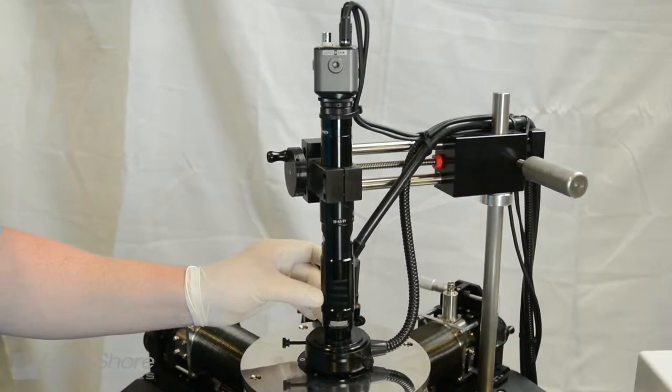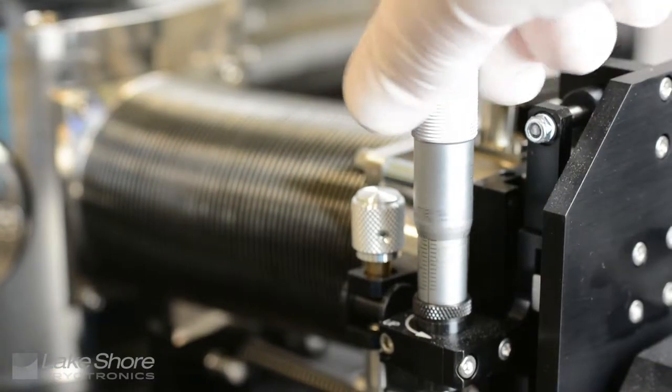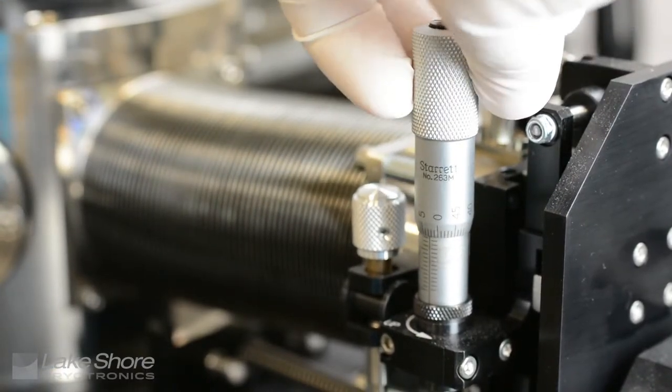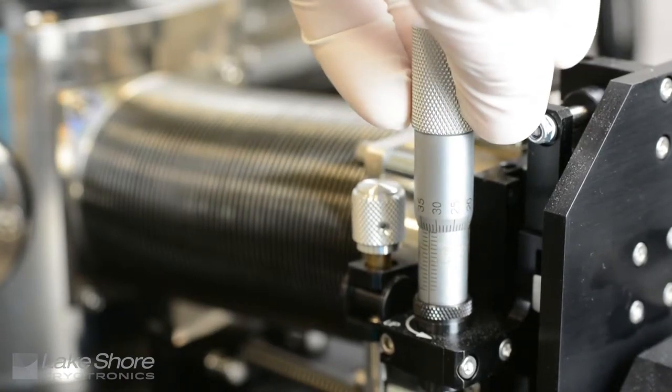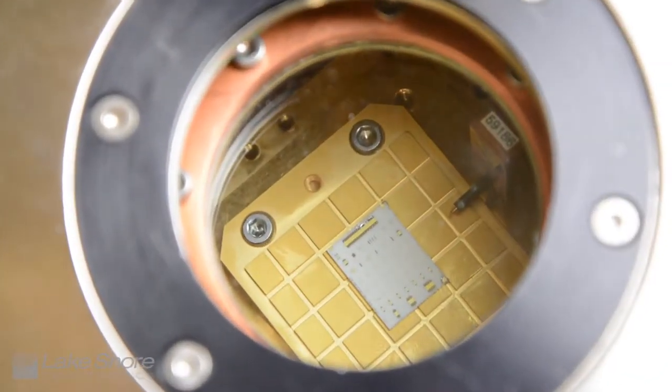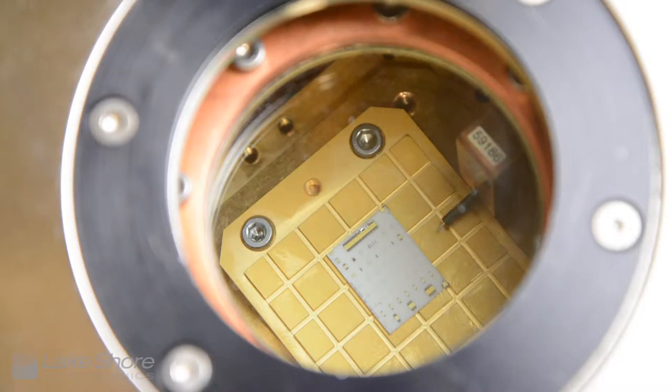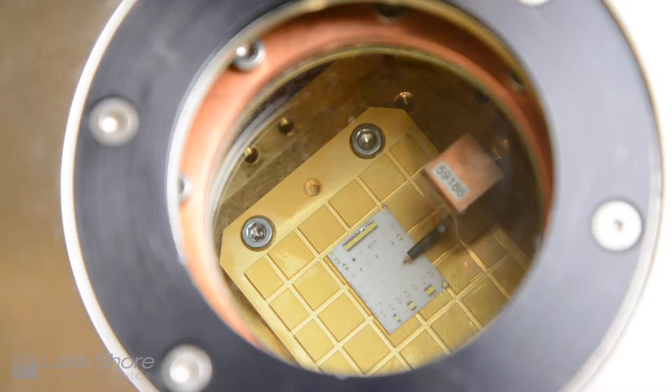In step 1, we will ensure the probe is visible through the viewport on the vacuum chamber and then use the z-axis micrometer to raise all probes above the sample stage enough to clear the sample landing pad. While visually observing through the vacuum chamber viewport, use the x-axis hand dial and y-axis micrometers to position the probe tip over the sample landing pad.